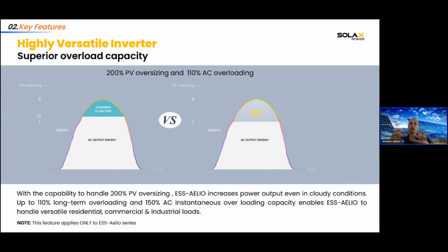So actually you can use 100 kilowatt PV at the same time with just a 50 kilowatt inverter. I think this is really important if you want to oversize your project a bit, compared to other batteries and ESS that cannot support 200% oversizing, because then you waste a lot of PV energy that you could store or supply to your loads.